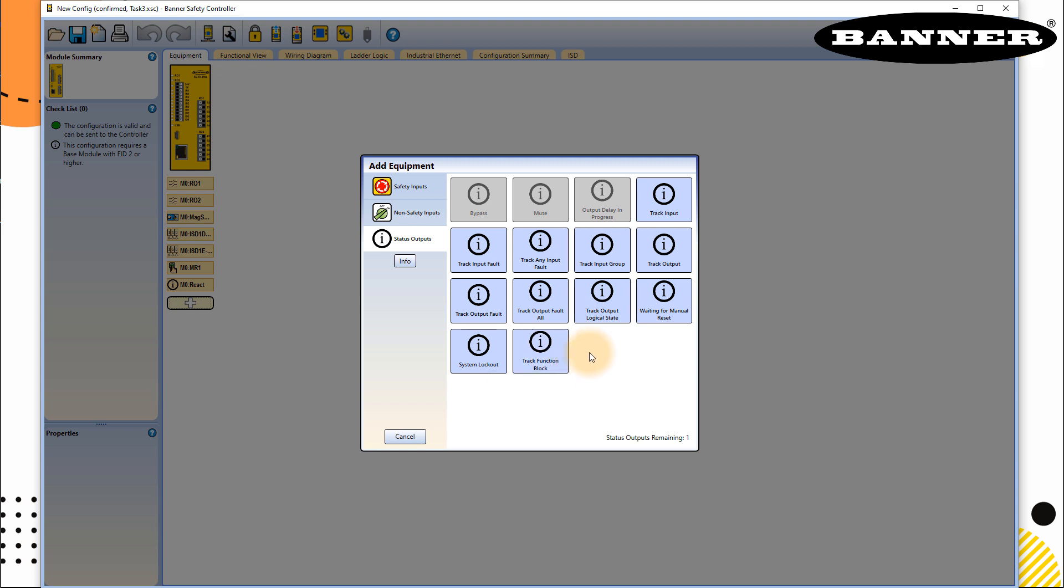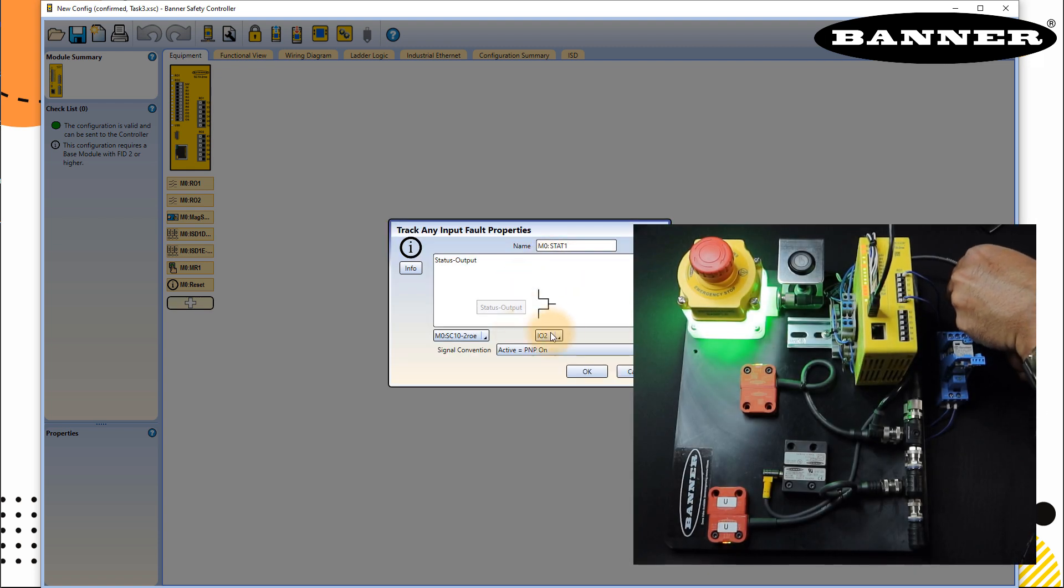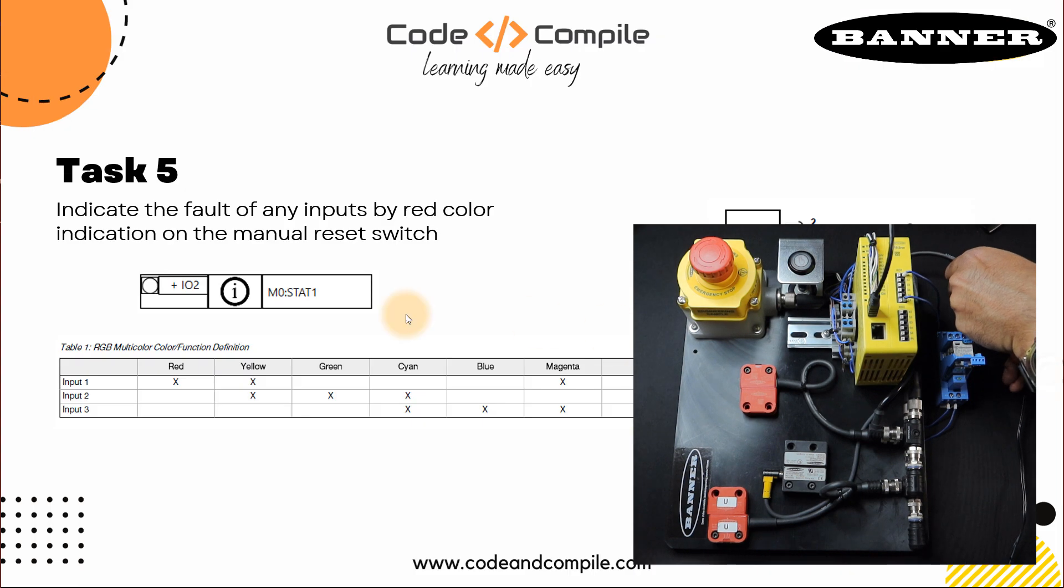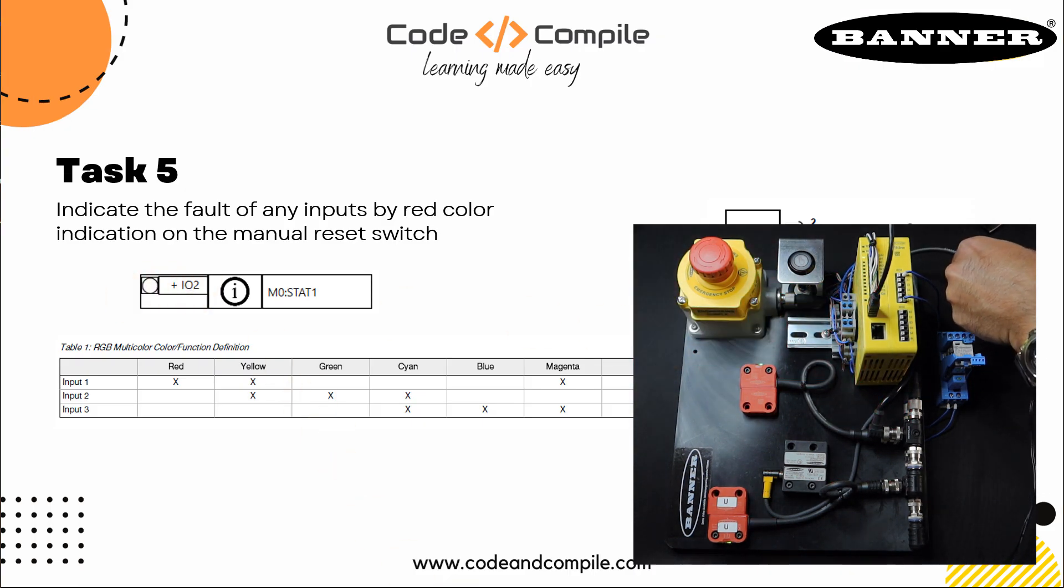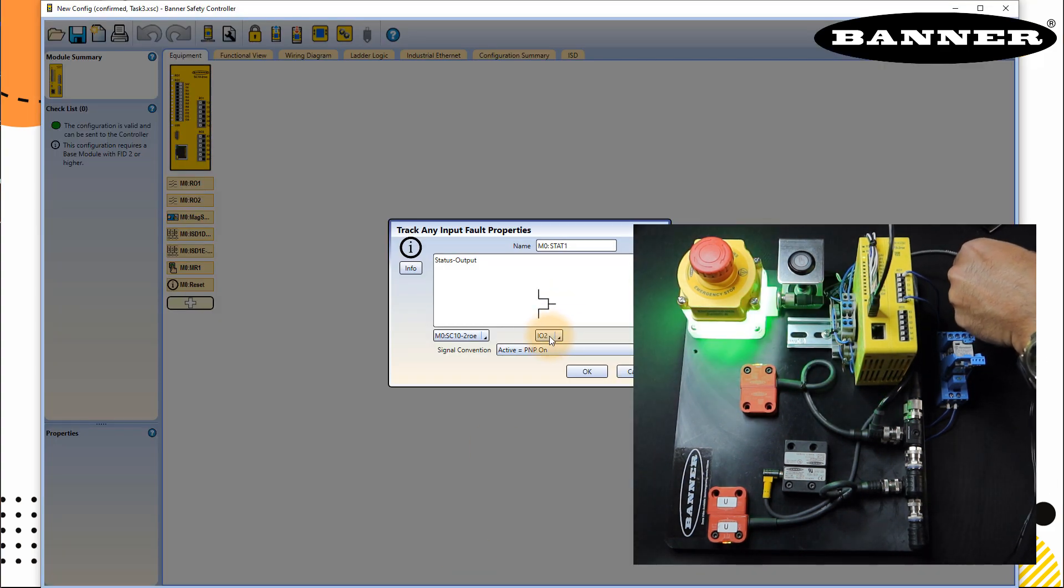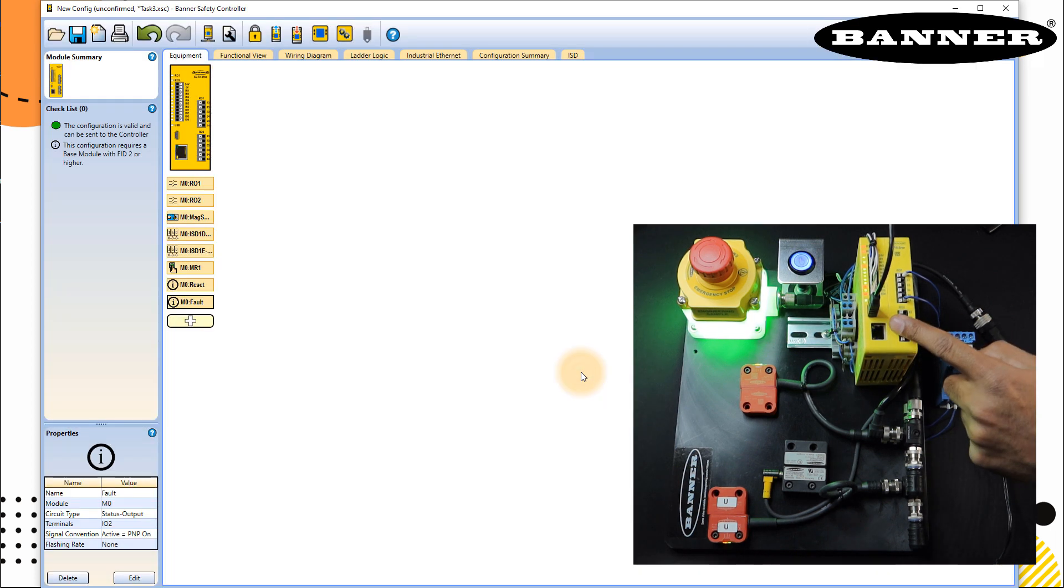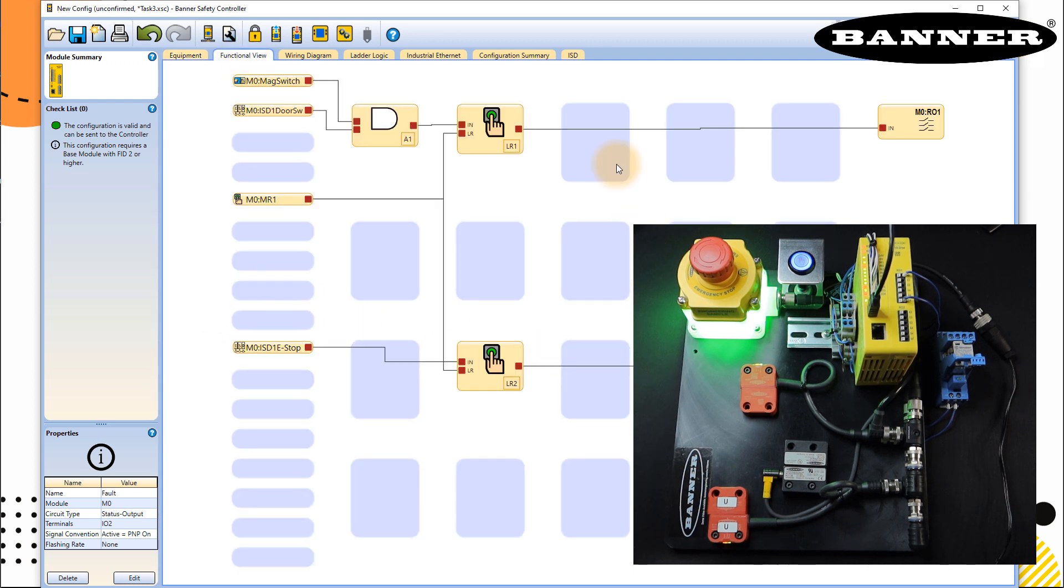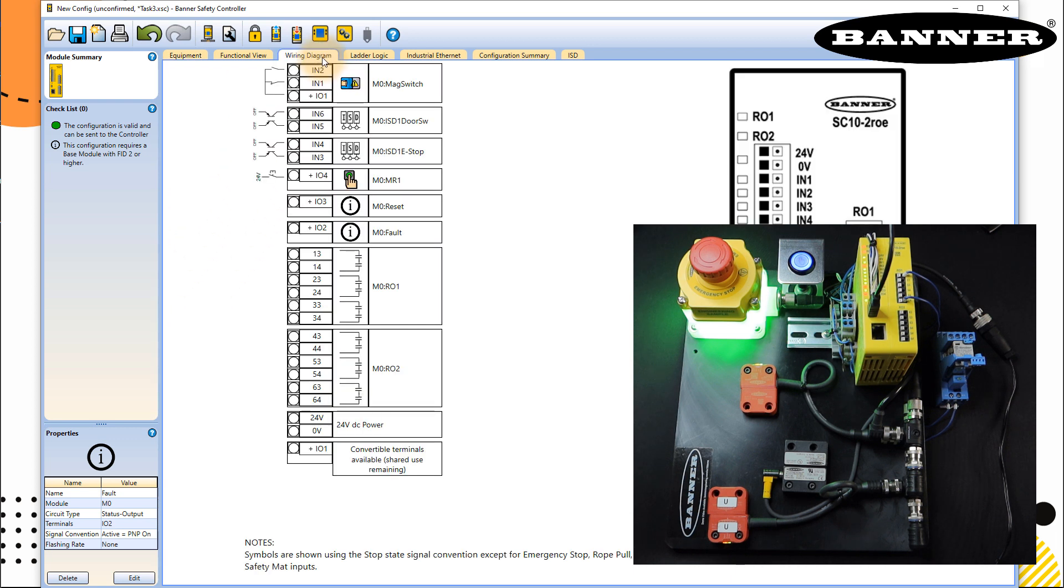Anyways, in our present case, we have to track any input fault. Click on this one. And this is your output. And remember where it is connected, IO2, which looks great. IO2 is this. PNP is on and here I will rename that to fault. Okay, and this is connected, you don't have to do anything in the programming. This is just the status output, it will connect here, you can just confirm by going to your wiring diagram.